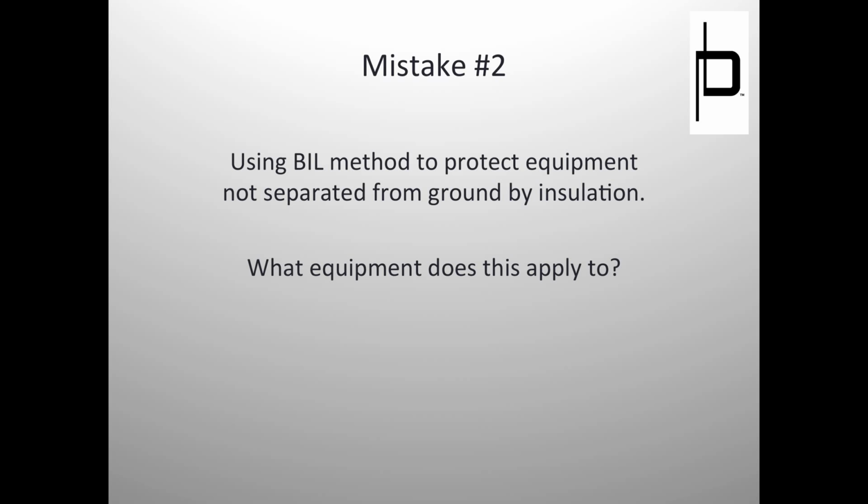The control house. What about the breaker tank? There's a lot of equipment in the substation that doesn't have a BIL. And if it doesn't have a BIL, should we really be using the BIL method to determine the stroke current? And I would say you really shouldn't.